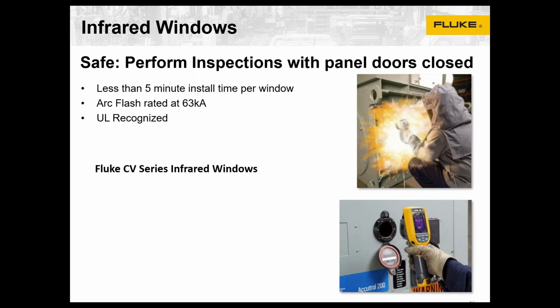Keep in mind that thermography is a line of sight technology, so you need line of sight to what you're seeing. If you're working on medium voltage applications, switchgear, or high energy applications, it might make sense to look into installing infrared inspection windows. They allow infrared energy to pass through, and if you put a camera up to them, you can see what is going on behind the panel, enabling you to work much more safely in high energy environments.